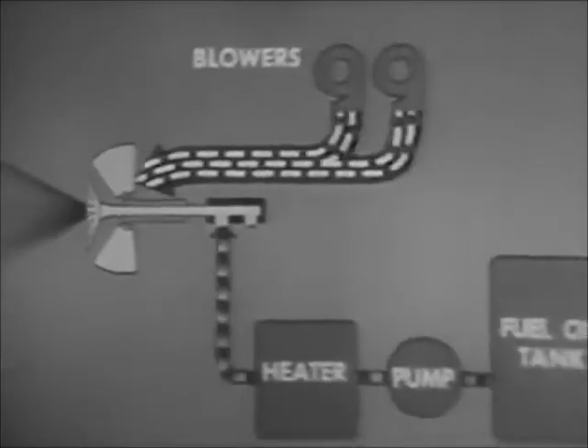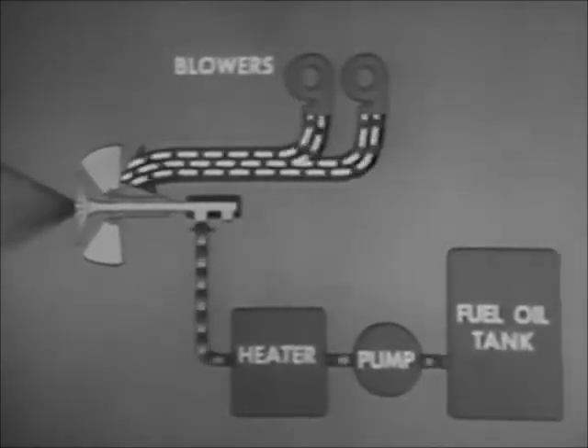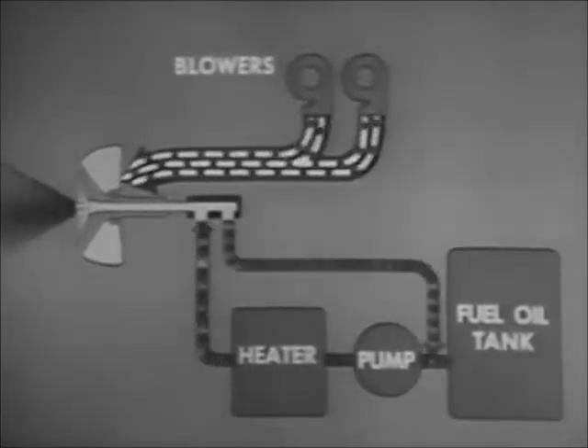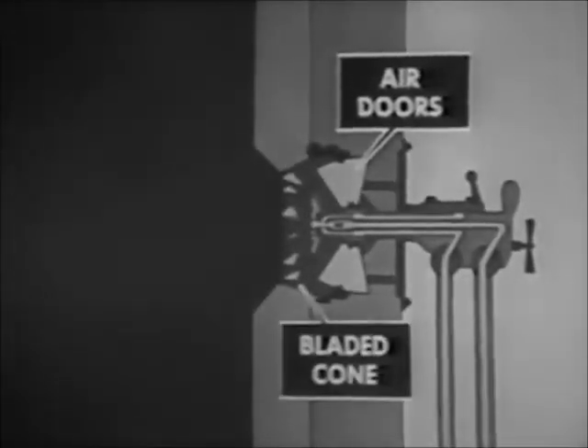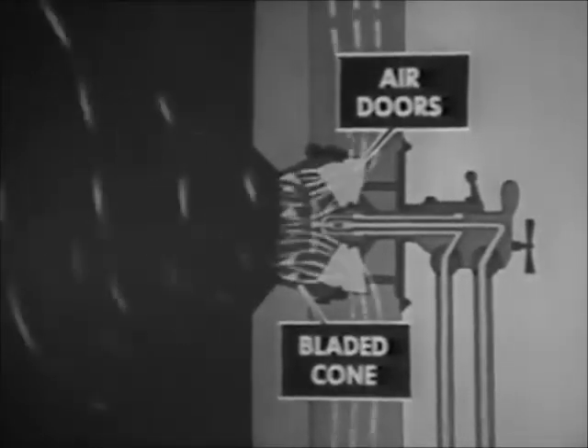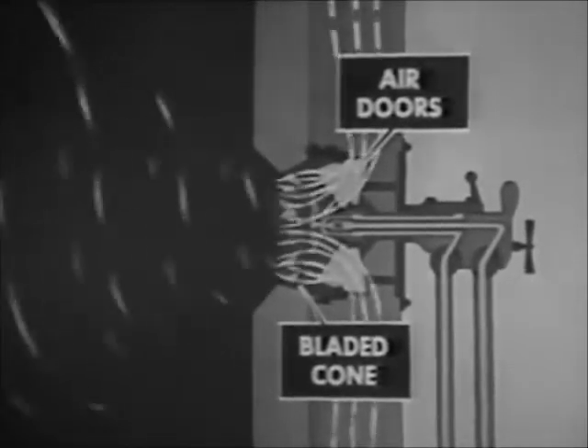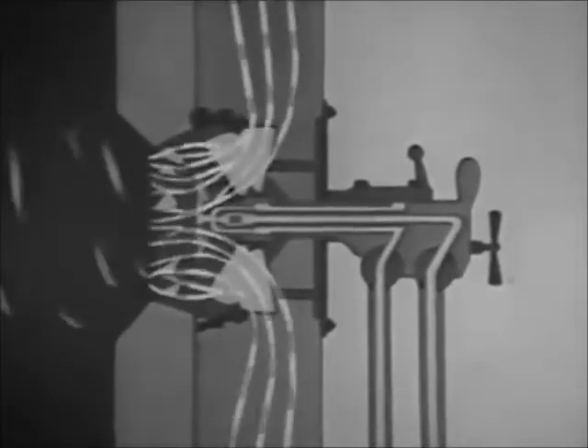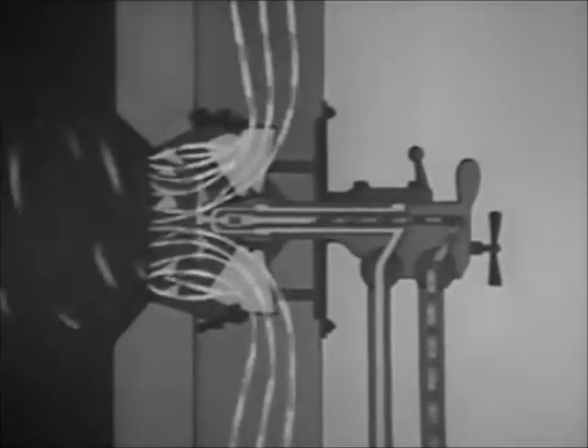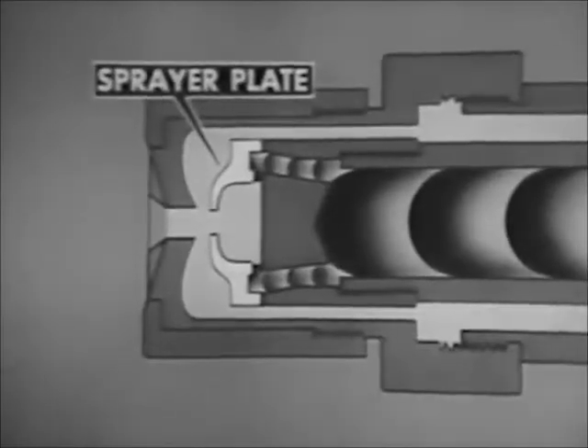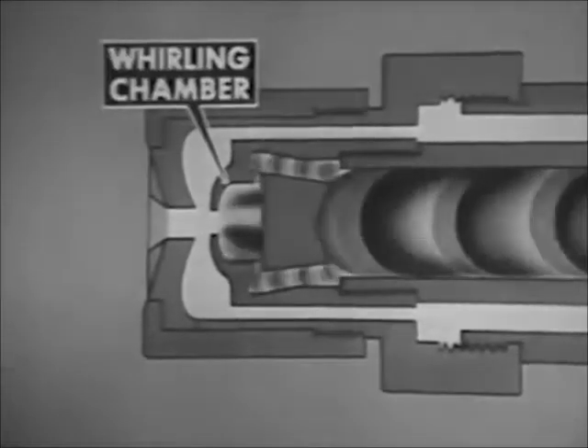In this type of burner — the return flow pressure atomizer — only part of the oil that goes through the burner is actually burned; the remainder returns to the fuel oil pump. Air doors and a bladed cone give the whirling motion to the air that enters the register to mix with the oil, as in the burner seen previously. The oil, heated and under pressure, is forced through the inner tube of the burner barrel to the sprayer plate, where the oil is rotated in the whirling chamber.